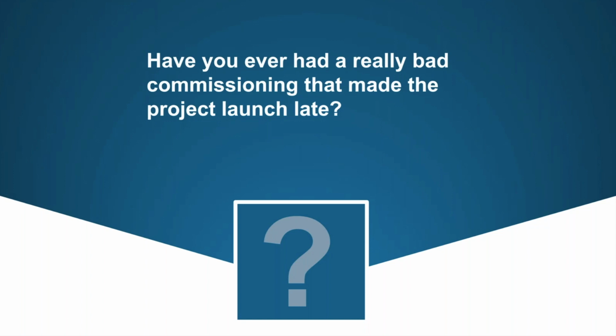Those types of things don't always get caught in the programming because it's the odd scenario, not the mainstream production parts every day. Here, the whole line went down because somebody opened up a safety fence or whatever the case may be, and how the thing reset was not tested. They killed a robot and did some damage to a column, and it was quite an expensive problem. That happens, and with some companies more often than they'd like to admit.